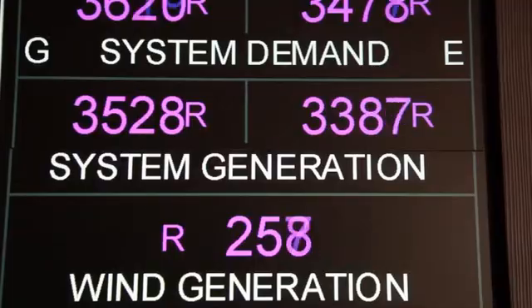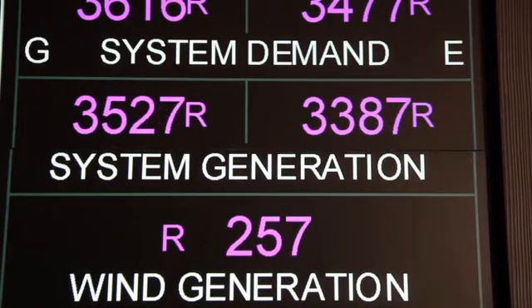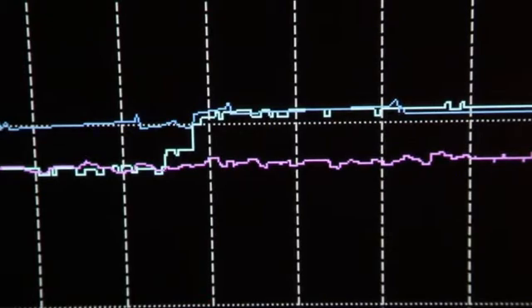In the control centre some 40,000 data points are fed in here every two seconds. We use this information to decide on the condition of the system and then respond to any events that should happen on the system. These may be in response to a lightning strike on a transmission line, the tripping of a generator or unexpected increase or reduction in system demand.